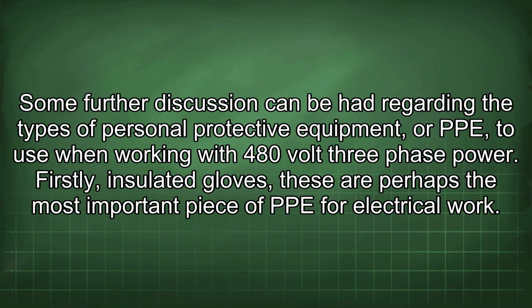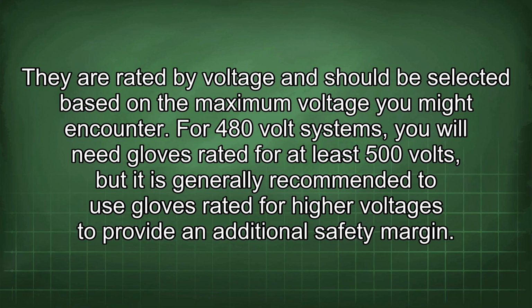Some further discussion can be had regarding the types of personal protective equipment, or PPE, to use when working with 480-volt three-phase power. Firstly, insulated gloves. These are perhaps the most important piece of PPE for electrical work. They are rated by voltage and should be selected based on the maximum voltage you might encounter. For 480-volt systems, you will need gloves rated for at least 500 volts, but it is generally recommended to use gloves rated for higher voltages to provide an additional safety margin.